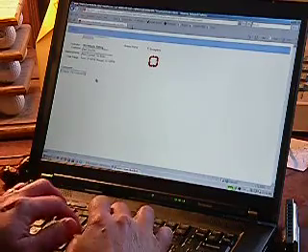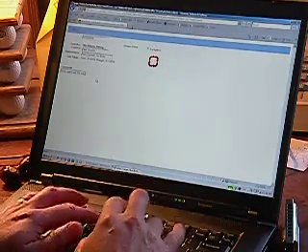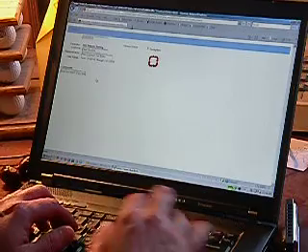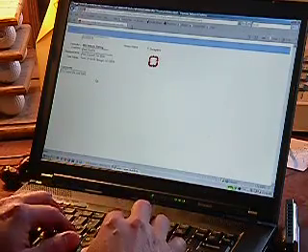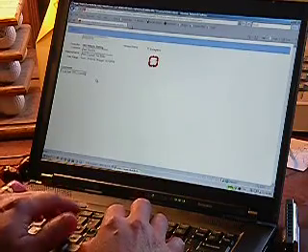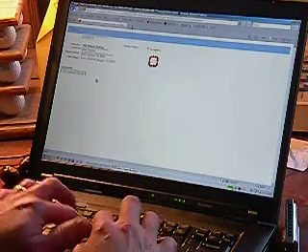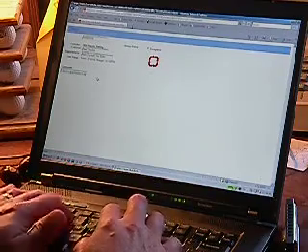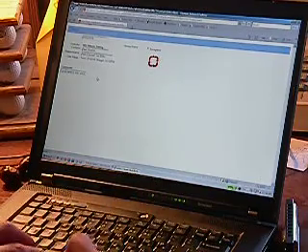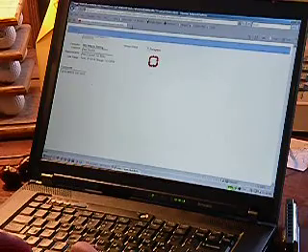The conductivity spike was the result of our attempt to control the seal leak. We corrected that, and the system has been in good balance ever since. This is not an exception. If it were an exception, I would click the exception box. I've made my comments. I'm not going to click submit.